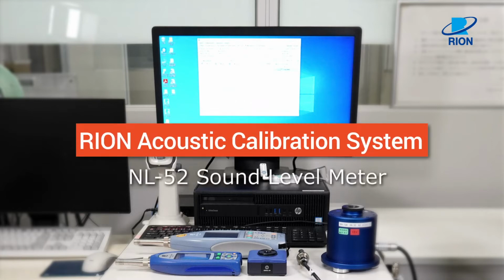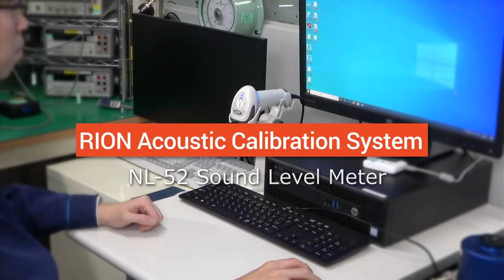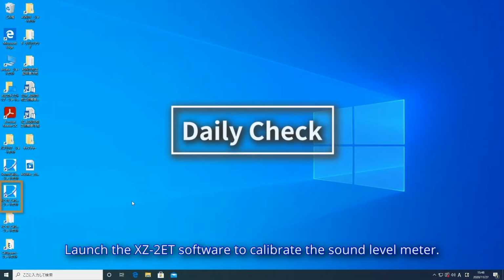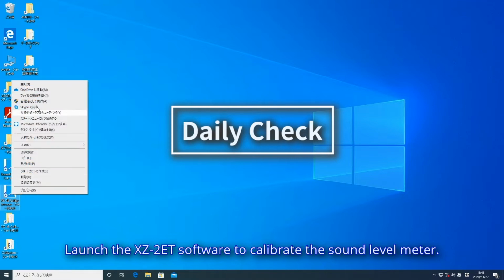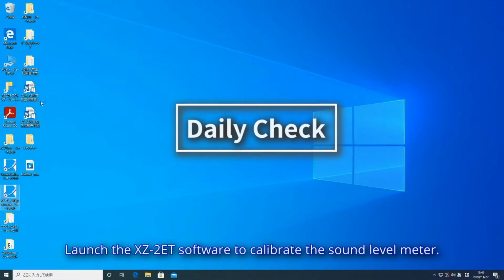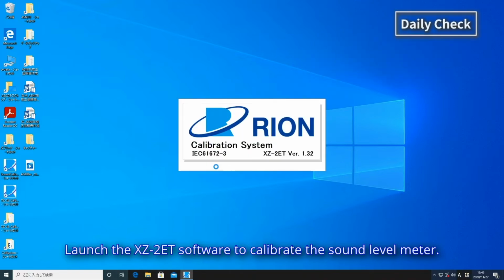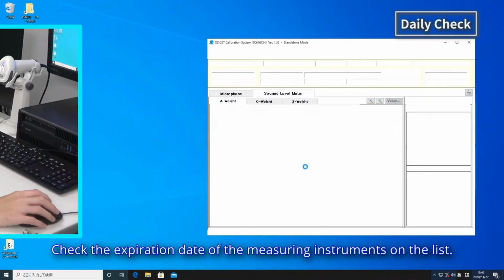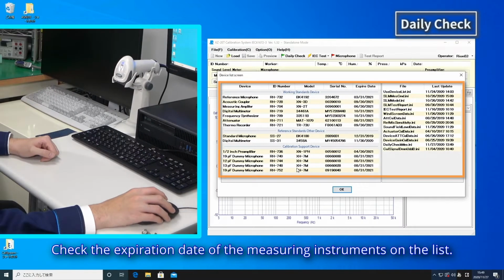NL52 Sound Level Meter Calibration Procedure. Daily check. Launch the XZ2ET software to calibrate the sound level meter. Check the expiration date of the measuring instruments on the list.